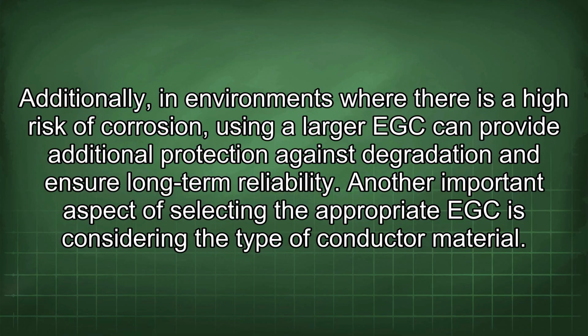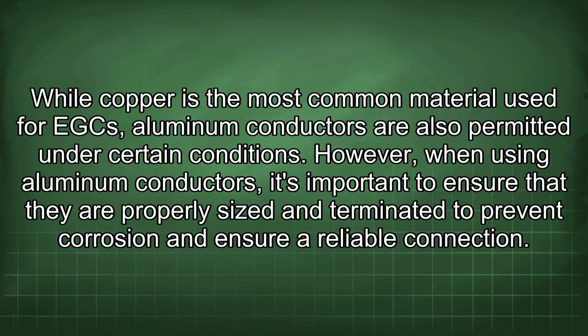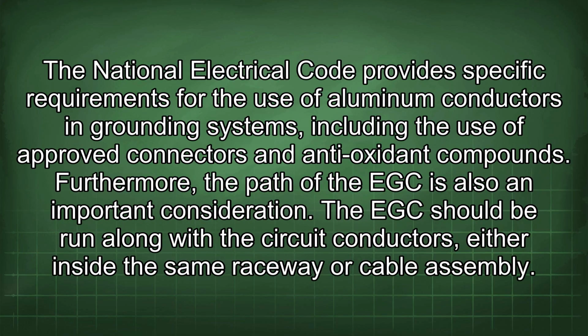Another important aspect of selecting the appropriate EGC is considering the type of conductor material. While copper is the most common material used for EGC, aluminum conductors are also permitted under certain conditions. However, when using aluminum conductors, it's important to ensure that they are properly sized and terminated to prevent corrosion and ensure reliable connection. The National Electrical Code provides specific requirements for the use of aluminum conductors in grounding systems, including the use of approved connectors and antioxidant compounds.